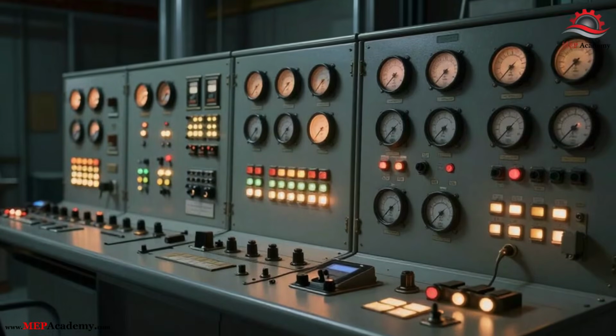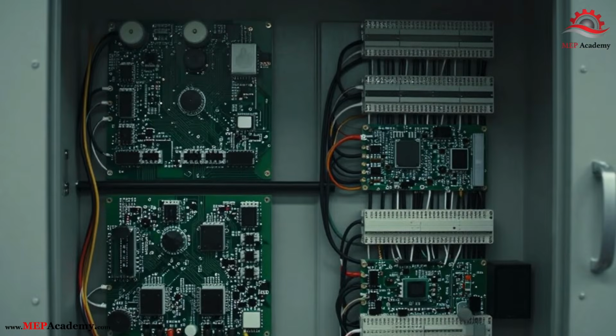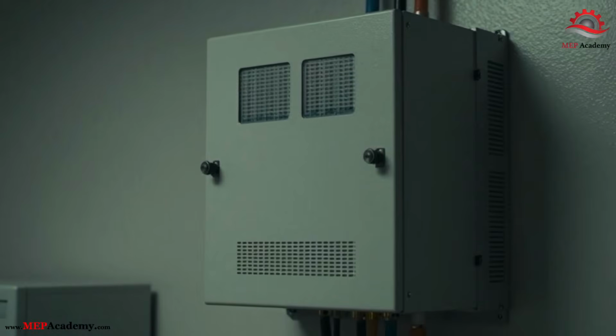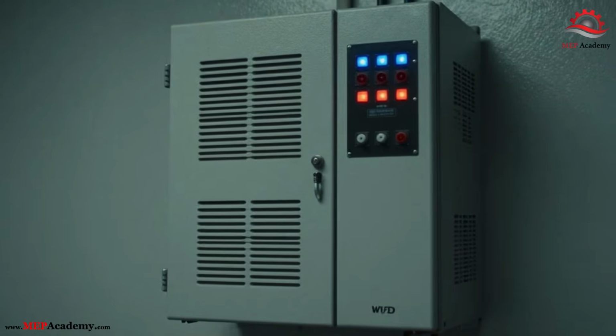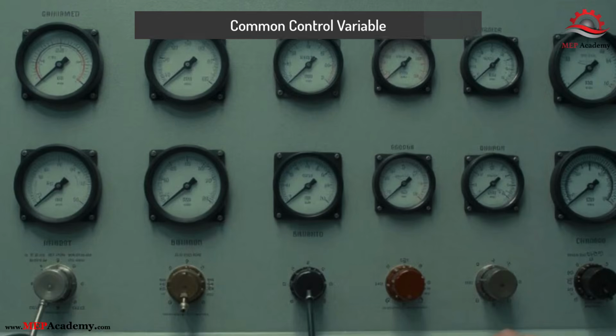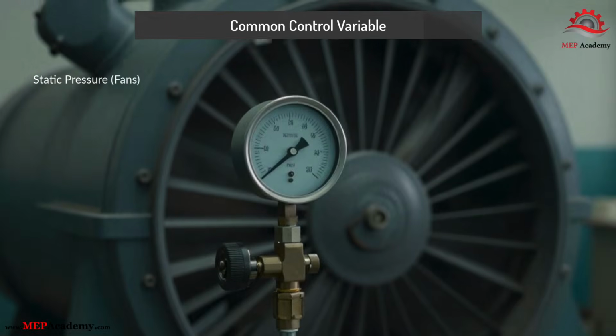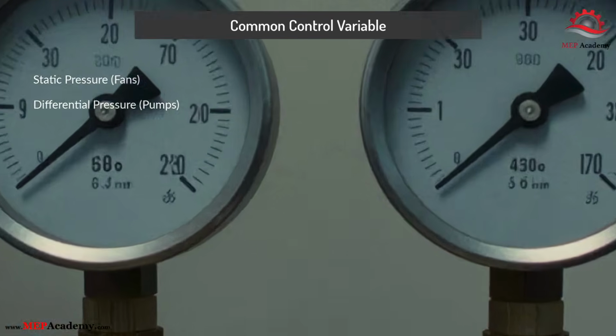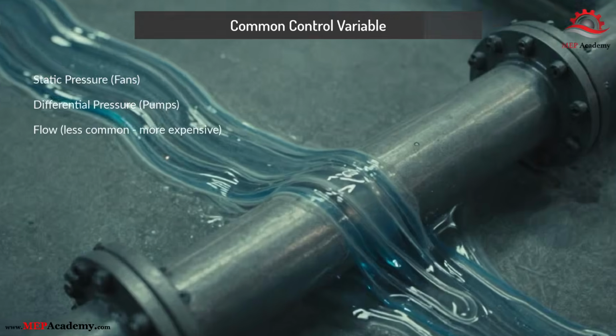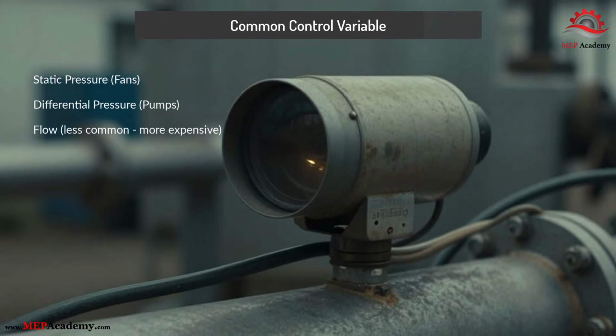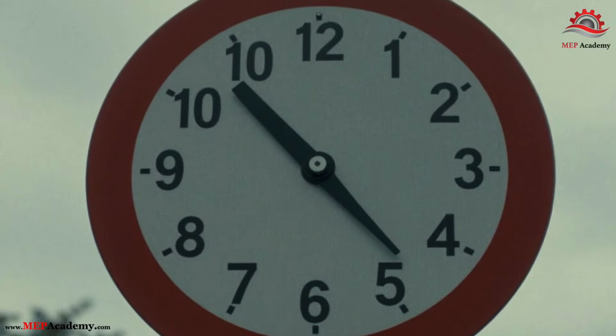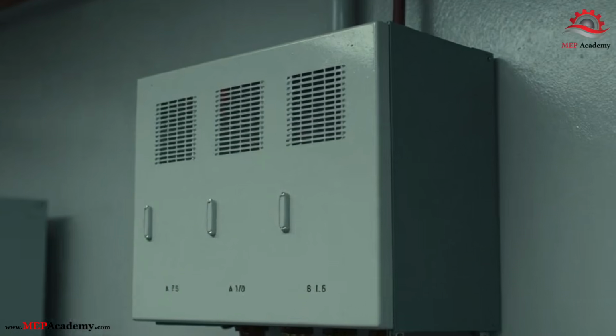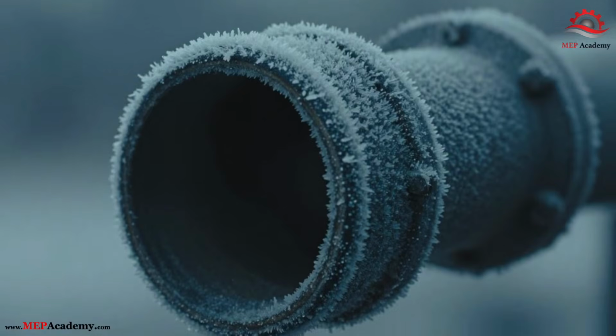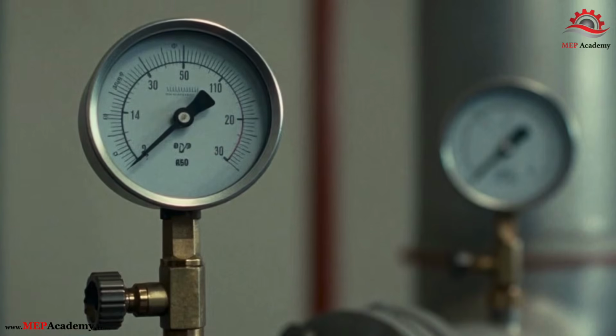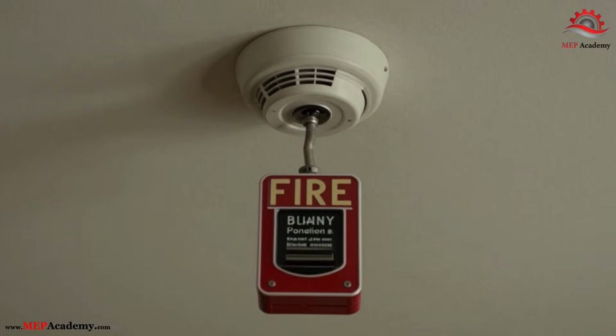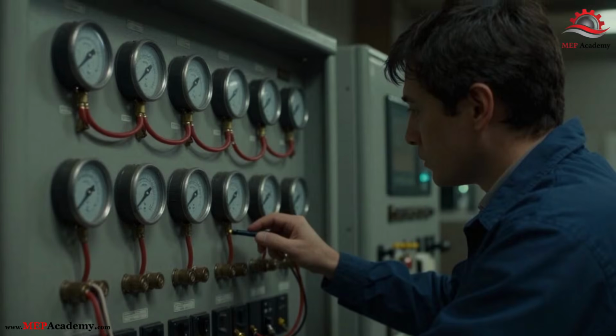Section 4. Controls, where most retrofits fail. The biggest mistake in VFD retrofits is controls logic. A VFD needs a process variable. If you don't have one, the drive will run, but it won't save energy. Common control variables: static pressure, fans; differential pressure, pumps; flow, less common, more expensive. Poor sensor placement leads to hunting, oscillation, and operator overrides. Minimum speed and safeties: every VFD retrofit needs a minimum speed limit, freeze protection, a proof of flow or airflow, fire and smoke overrides. If these aren't clearly defined, commissioning becomes guesswork.